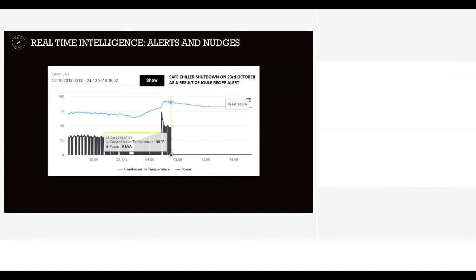Here you can see the condenser entry temperature went to 107 degrees Fahrenheit, somewhere around 42-45 degrees Celsius, and the machine tripped in safety. The temperature limit of that equipment was overrun and the chiller tripped because there was nobody to fetch the data in real time and alert someone that the temperature was rising and the chiller would trip. This is an actual live incident that happened in 2018 at one of our sites in India, in Delhi.